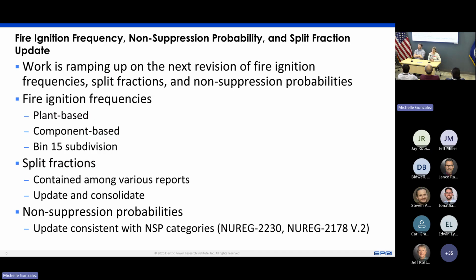This covers the scope of the update of the fire ignition frequencies. We want to trend the fire events using the last decade of data, and we'll provide both plant-based and component-based calculations so as an analyst you'll have a choice. In concert, we'll also update the non-suppression probabilities with the fire ignition frequencies. One thing we didn't do well in 2169 was update the split fraction, so that will also be updated and consolidated. The intention is to make this new revision of the fire ignition frequencies have all the data you need to update the fire PRA.